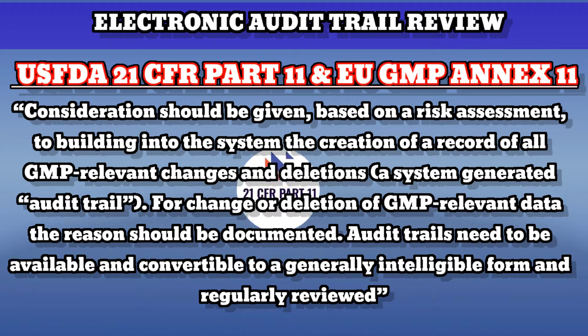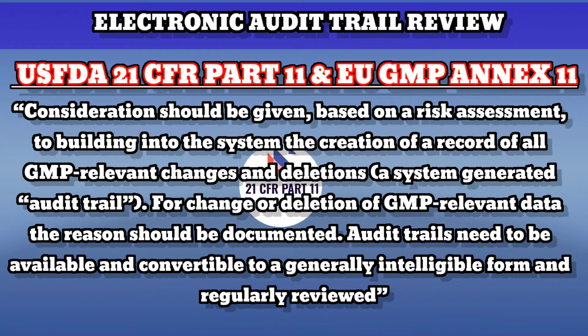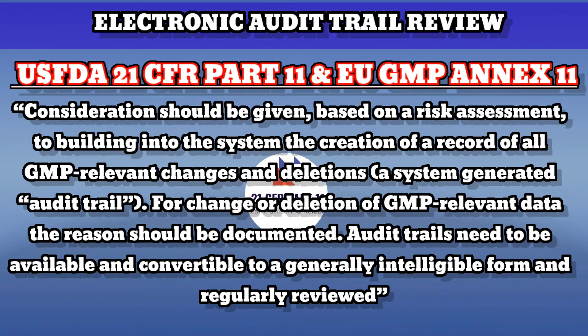The US FDA 21 CFR Part 11 and EU GMP Annex 11 Clause 9 request that consideration should be given, based on a risk assessment, to building into the system the creation of a record of all GMP-relevant changes and deletions — in short, a system-generated audit trail. For any change or deletion of GMP-relevant data, the reason should be documented. Audit trails need to be available, convertible to a generally intelligible form, and regularly reviewed.